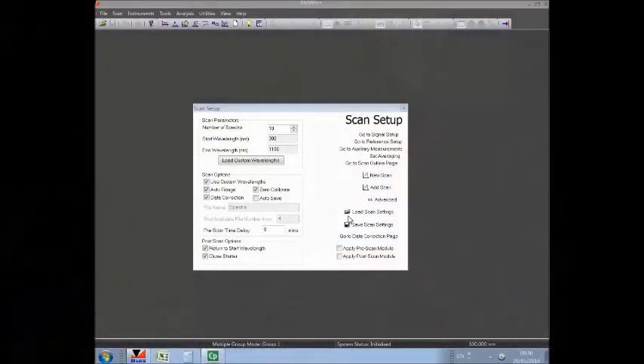Now if we look to BenWin Plus, in normal circumstances one would perform, if a measurement 200 to 1100 is required, the calibration of the CL6 followed directly by the calibration of the CL7 or vice versa, without applying data correction in between. I demonstrated the use of data correction where only the CL6 calibration is required. I must switch this off in order to perform the calibration of the CL7 lamp 200 to 400 nanometers.